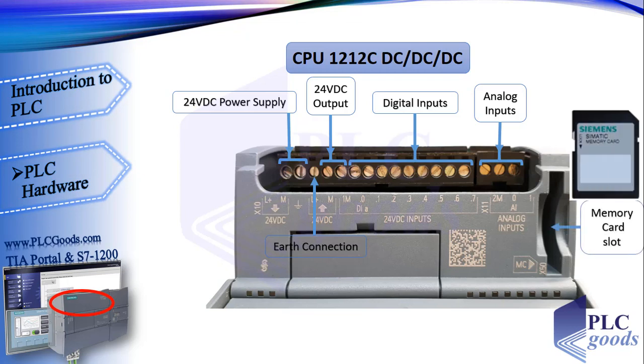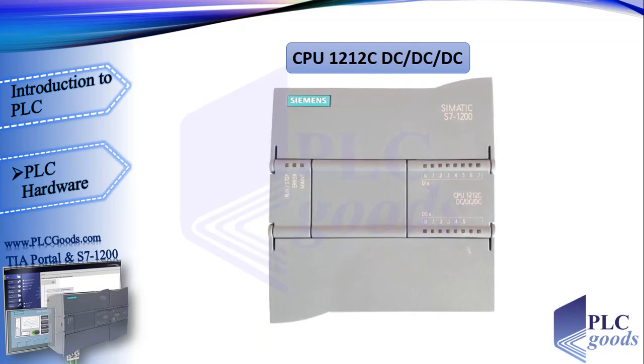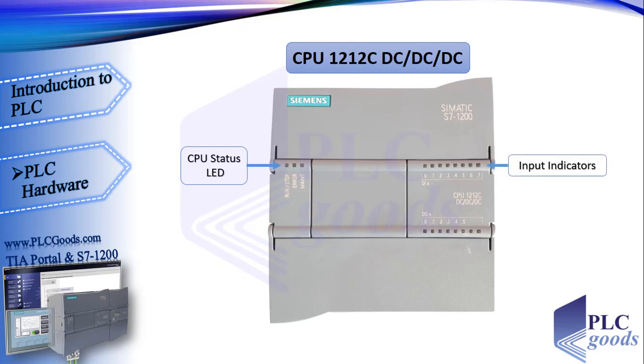Analog sensors give us a signal such as 0 to 10 volt DC or 4 to 20 milliampere. A memory card may also be needed, used either as a transfer card — to copy a program to the CPU's internal load memory without software — or as a program card, serving as external load memory for the CPU. On the front of the PLC there are LEDs: the first shows whether the CPU is running or stopped, the second indicates any configuration error, and the third is for maintenance requests. On the right side, LEDs indicate which input is on or off.